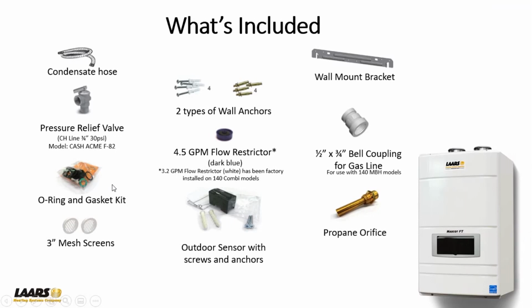The other gaskets, all of these are quick release components. So if you had to replace a component and you tore a gasket or lost the gasket, dropped the gasket, we give you additional gaskets. So that's why they're there. We'll give you the 3-inch mesh screens. This is all included. 2 types of wall anchors, the wall mounting bracket. Again, we talk about a propane orifice shipped with every boiler, and an outdoor sensor. Why? Because Department of Energy, DOE, mandates that, especially in residential, you have to use outdoor reset. So we'll get into some of that.